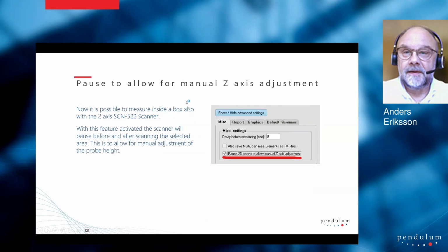Two-dimensional scanners can now measure inside a box and allow time to manually move the probe up and down, because we pause the measurement at the first measuring point and at the last measuring point. So now you can measure inside a box also with two-dimensional scanners.